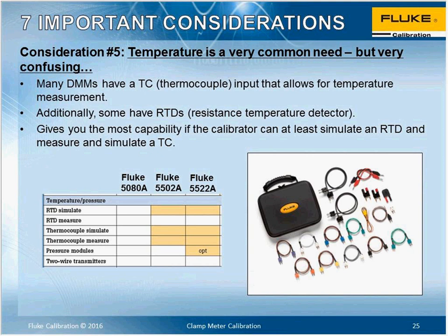As I said earlier, a lot of the handhelds that we offer today at Fluke do have some sort of temperature function, whether it's RTD or thermocouple. So we put this into our multi-product calibrators, and I know a lot of the other manufacturers do as well. The guide here is to make sure the calibrator has enough accuracy in its temperature function to cover the workload. It takes a little bit of figuring out, but what you want to make sure of is that the product can at least simulate an RTD and simulate a TC.